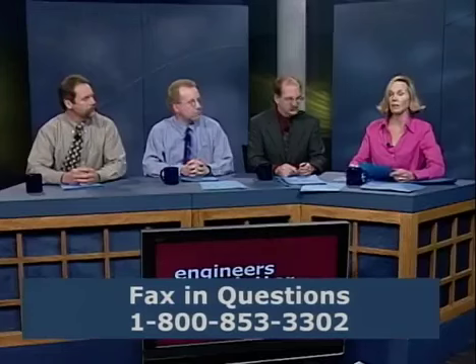Thanks, Court. Dave, this next one's for you. In a decoupled chiller plant with several heat recovery chillers, can more than one heat recovery chiller be placed on the load side of the bypass line? The answer to that is yes, and that's the best place to put your heat recovery chillers. If you have more than one, they should all be there. And in fact, you might want to consider placing one of the cooling only chillers on the load side. That way it'll be the one that gets the diluted temperature.